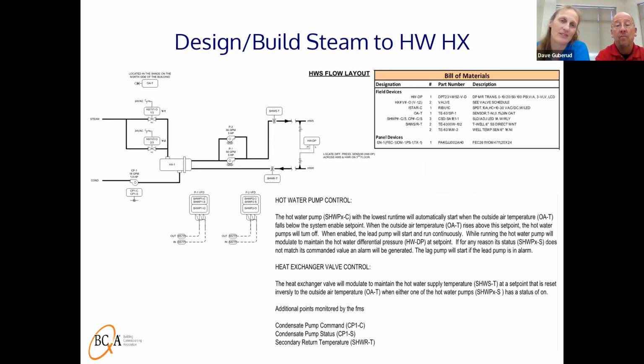So here we have a design build steam to hot water heat exchanger. You can see we've got steam piping with the 1/3, 2/3 valve into the heat exchanger, and leaving, we've got 2 parallel pumps. And then we've got the hot water system, and then a DP sensor out there for control. And then the sequence of operation there states things in a real, I'll call it generic fashion. And if you can look, and maybe the screen resolution isn't the greatest, there is not one actual number in there from a temperature perspective or pressure set point perspective at all. So we need to work to drag that kind of information out.